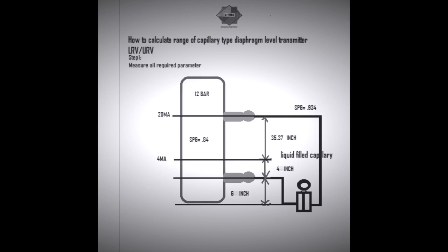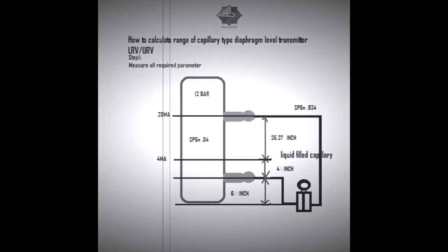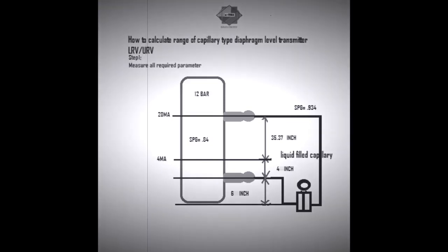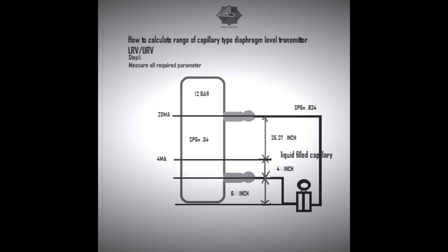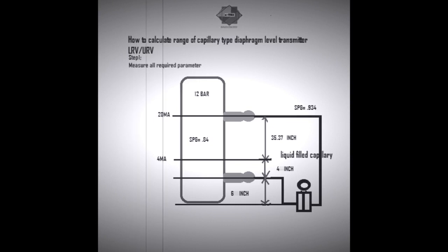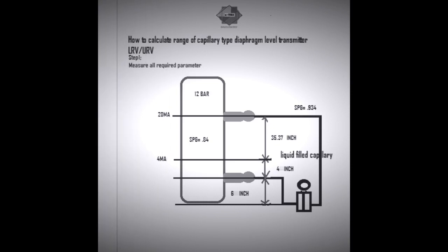As seen in the picture, the vessel scrubber has 12 bar pressure. The LP side tapping is located upside, which is 36.37 inches above the HP side tapping point, and the HP side tapping point is located downside. The process gas specific gravity is 0.84 and the capillary liquid fill specific gravity is 0.934. The transmitter is mounted 6 inches below the HP side tapping point, as shown in the picture, and the zero percentage point is 4 inches above the HP side tapping point.